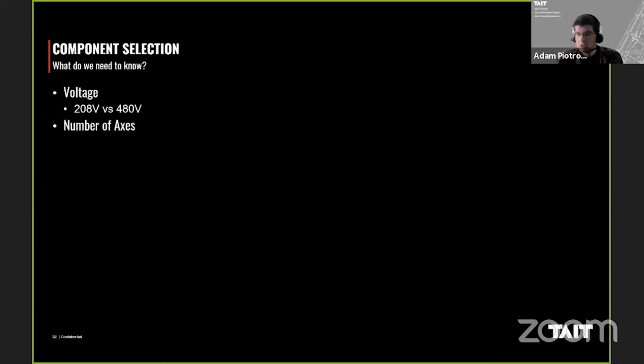Things like the number of axes. I talked about the Navigator nodes and not only their form factor, but their compute power. Every time we add an axis, we need to have a motion task looking at its I/O, looking at the encoder, doing the closed loop positioning of that, and sending that set point to the drive. So as we add more axes, we have more processing we need to do, we need bigger nodes. That may come down to either just having the biggest node we can with the most CPU, or do we start looking at a distributed system and putting nodes around the building, segregating them to very specific tasks—be it an MCC has its own node, or maybe the grid gets a node, the fly loft gets a node, and the basement or lift system gets a node.